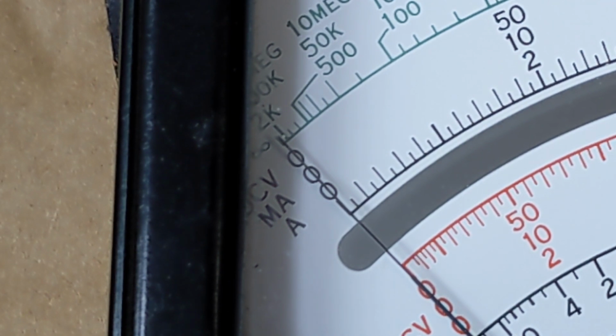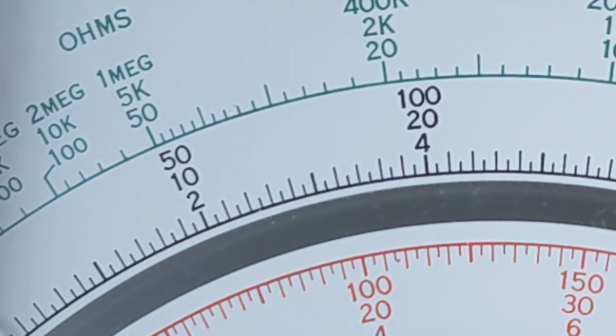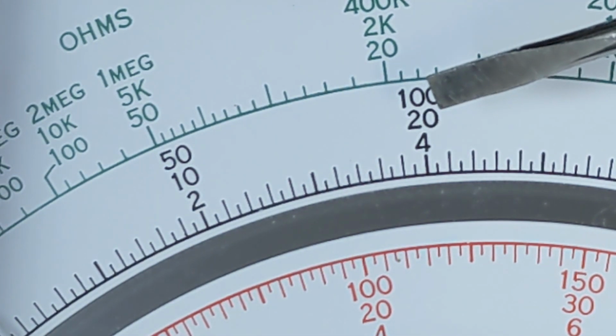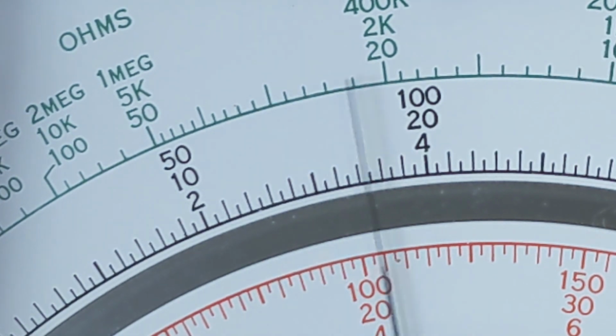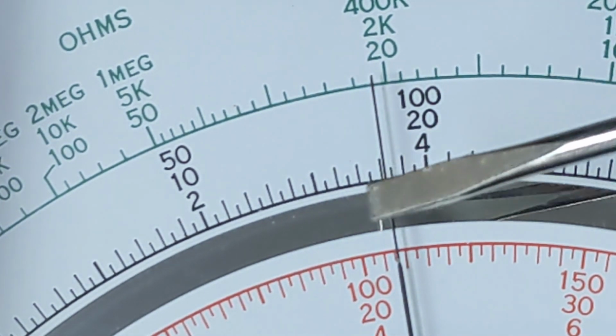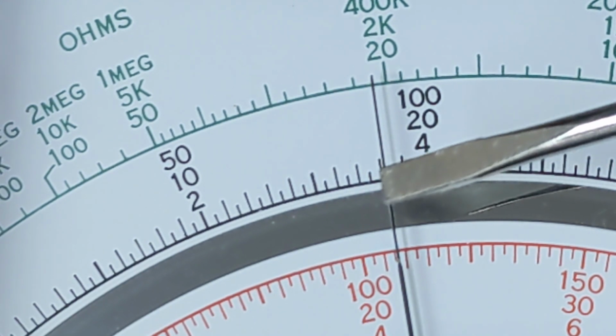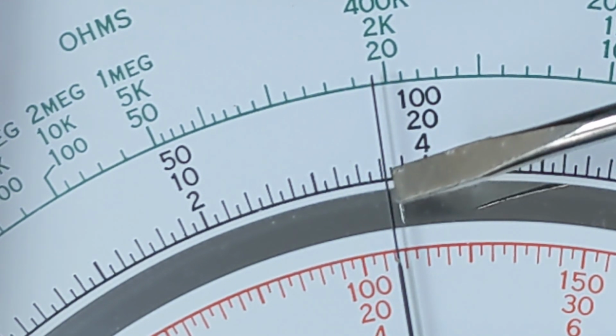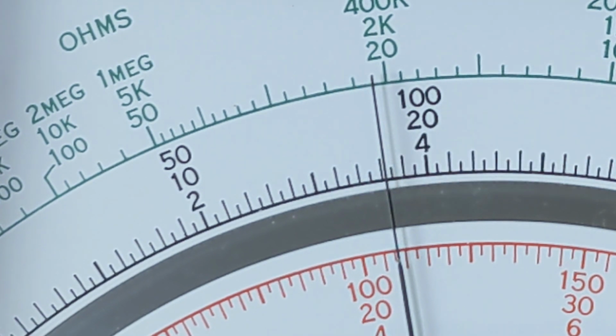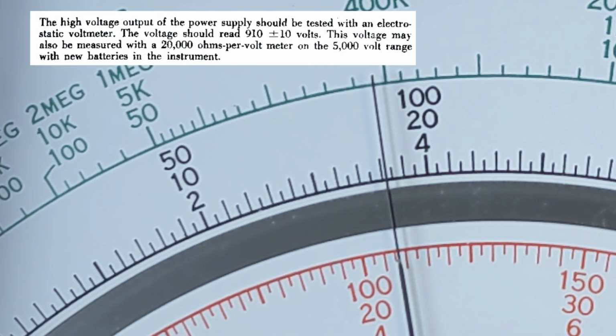So first making sure that the 0 point is set correctly. There's a little screw you turn in the middle of the meter for that. It's now over where 1000 volts is, so this 100 is 1000 volts. And right about where the needle is, that would be 900 volts at that major tick mark. The next smaller one is 925, and we're looking for 910 plus or minus 10 volts per the manual.